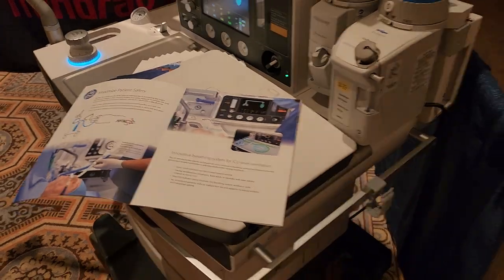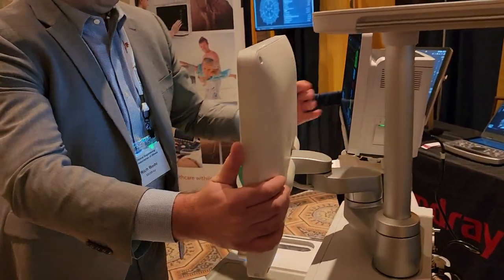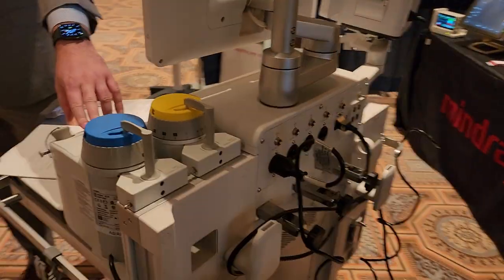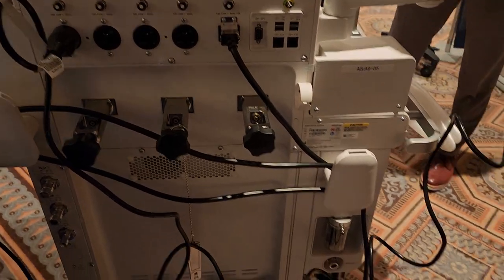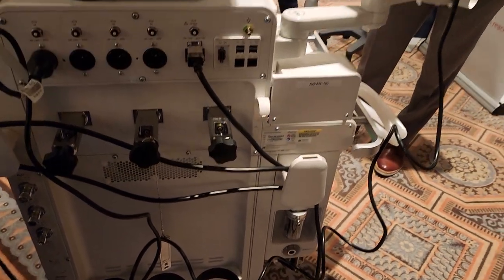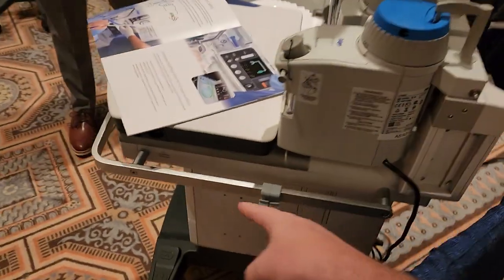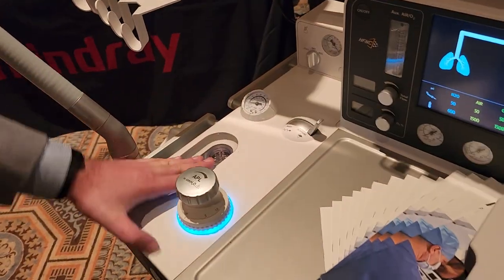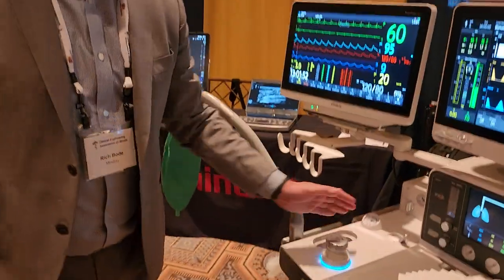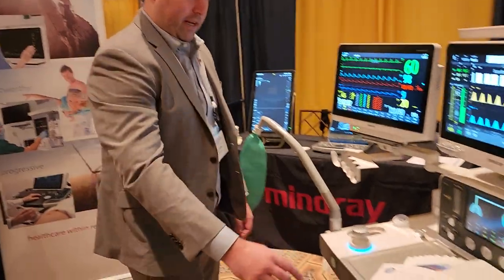This itself is a 360-degree rotating screen, so they don't have to rotate the machine. With the A9, which uses electronic vaporizers, you can actually control the vaporizers from the screen itself. Let's take a look down the back — we get the accessory mounting options, rails built in, more rails. Flow sensors are about every three years to be replaced. There's no drive gas — there's a warming sensor in there, a warming plate to prevent condensation. Thank you very much for giving me a walkthrough.